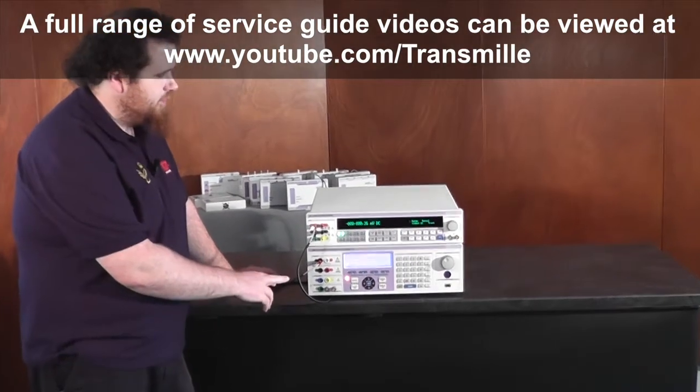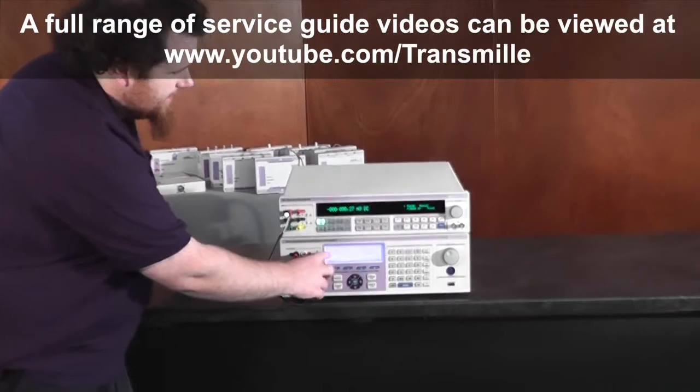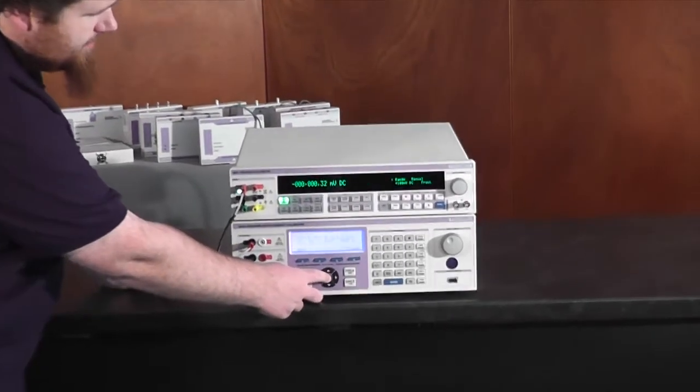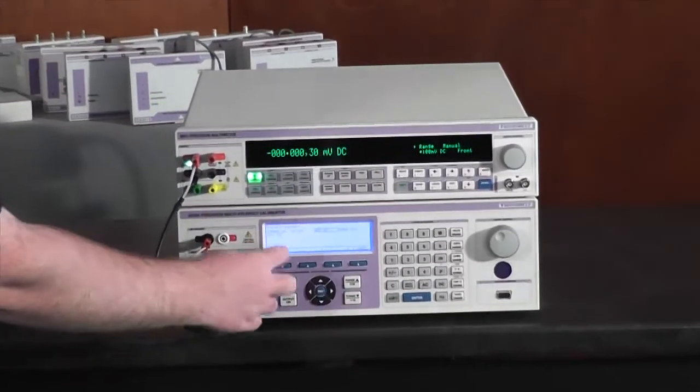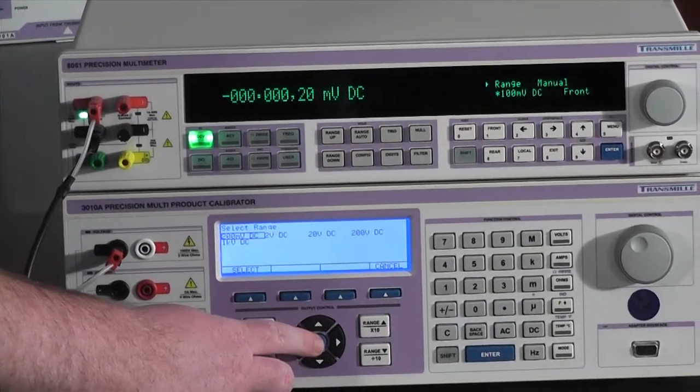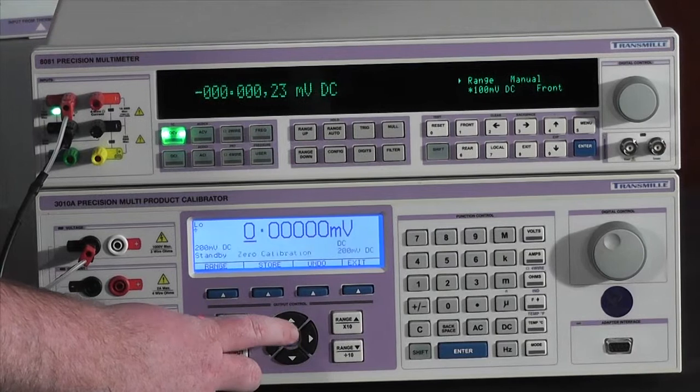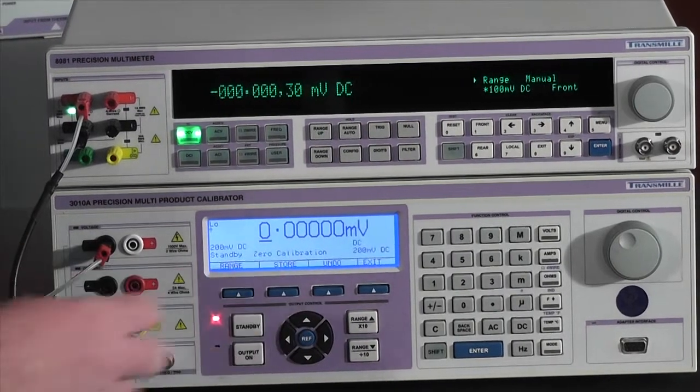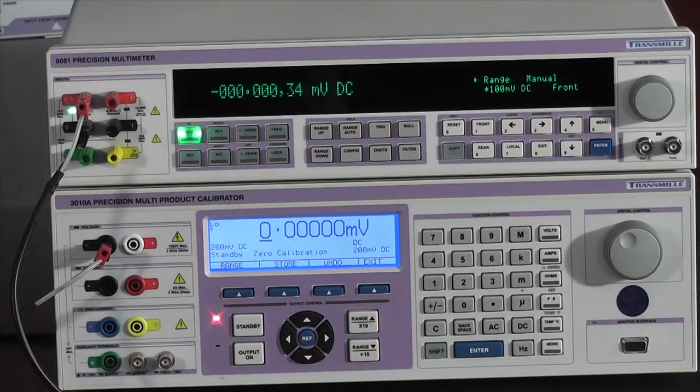Once entering the calibration menu, simply select DC volts from the screen, select the range that you want to adjust. In this case I'm going to select 200 millivolts, and the first calibration point will be the zero calibration.